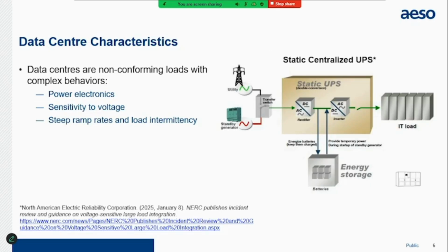Before discussing the requirements for data center interconnection, it's better to understand some high-level characteristics of data centers. In many jurisdictions, data centers are categorized as non-conforming load, which behaves quite differently compared to commercial or industrial load. This is because of the power electronics components in data centers and their sensitivity to voltage, as well as steep ramp rates and intermittent load profiles.